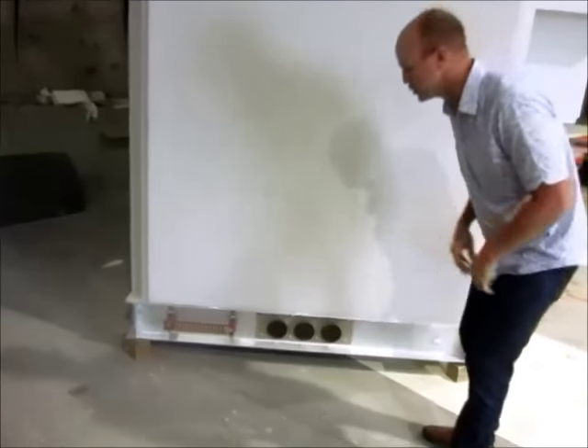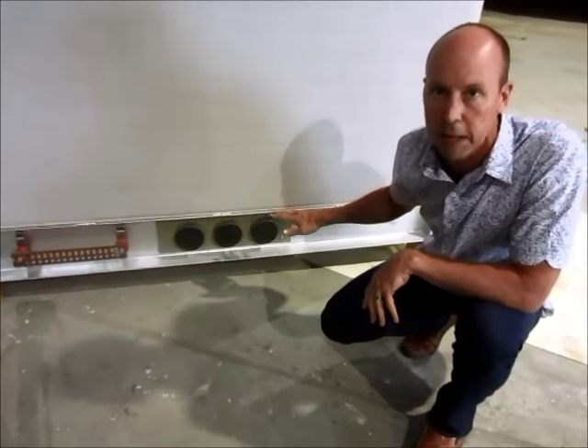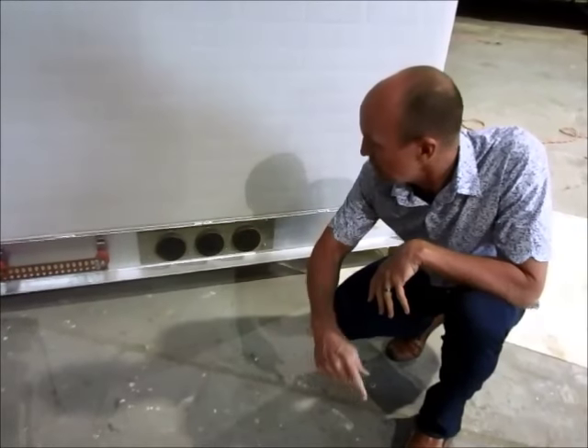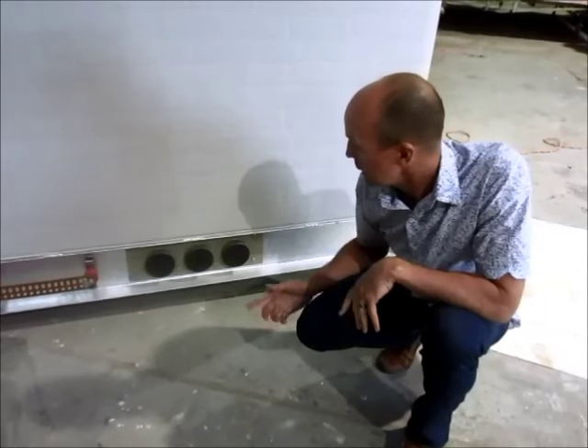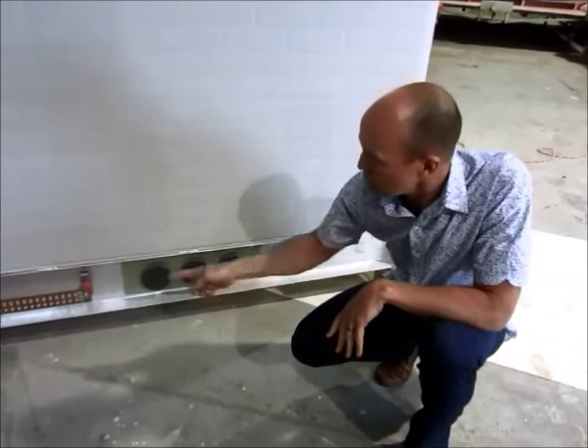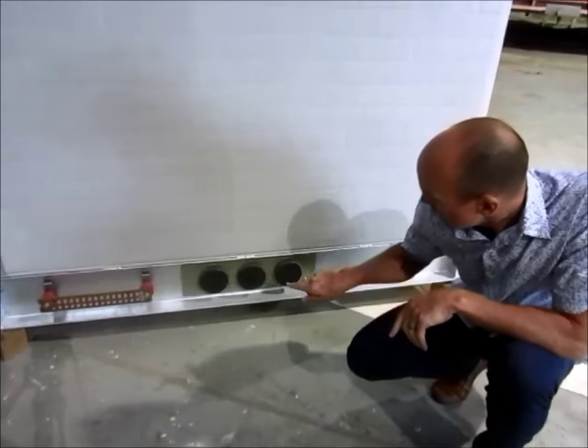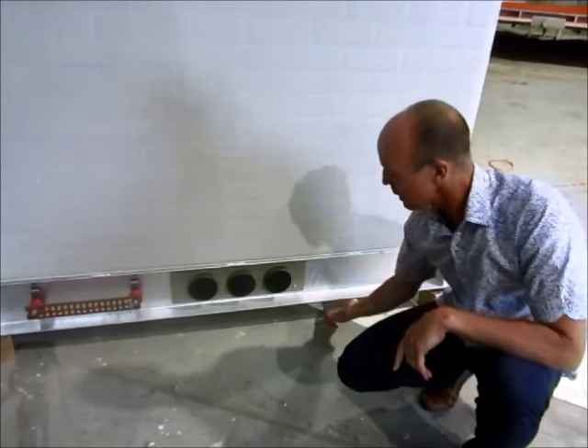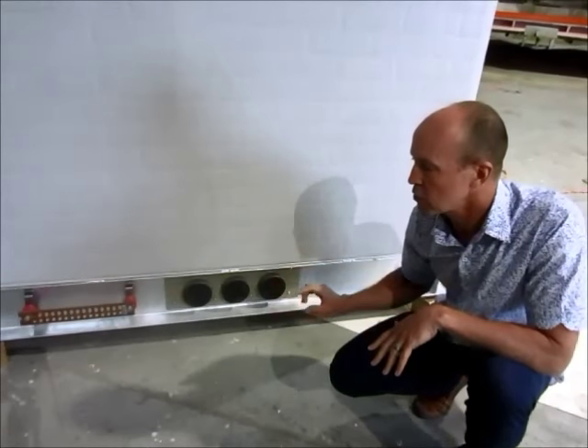This is a telecommunications shelter, so this steel base is not only the floor and platform for the enclosure, but we also have cable ports that allow us to bring in RF cabling or fiber optic cabling into the floor, which is much more secure than from overhead. There's also a grounding bar here for special electrical grounding. The floor cavity has a walking surface here, and there's a bottom panel down here, and in between there's a cavity that's available for chasing wires, and it's also insulated.